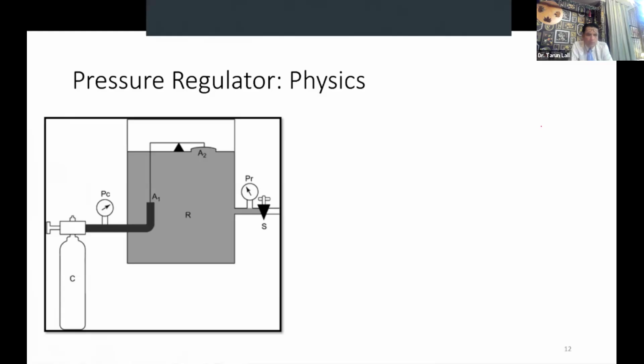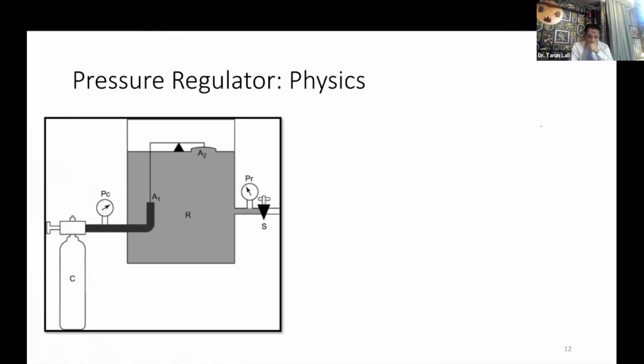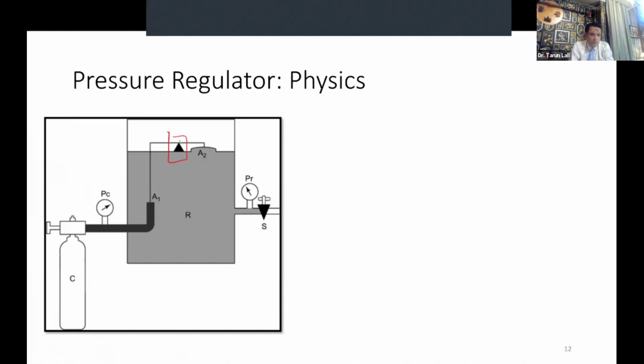Now the pressure regulator works on the simple principle that force upon area is equal to pressure. Or, as you all know, the definition of pressure is force per unit area. The pressure varies as per the area of the diaphragm to which it is exposed. Now, if we look at this fulcrum, when there is no gas flow, on both sides of this fulcrum the forces are balanced.